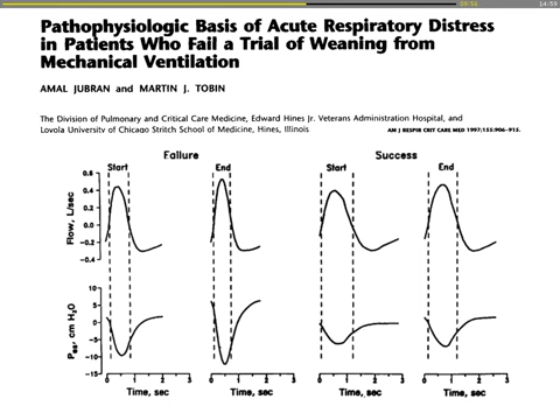Had I seen and known this difference from the start, I would not have let the patient fail. I would have stopped earlier, or I would have increased the support. Because I can adjust the amount of work the patient does and the amount of work the ventilator does. If I see that the patient is working too much, the simple solution is to increase the amount of work done by the ventilator.